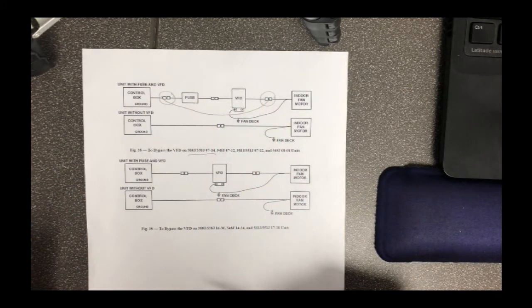Why? Because those fuses are not large enough to handle the locked rotor amps of this motor starting without the drive on it. You're going to blow those fuses, and they're not cheap fuses. So if you have the inline fuses, bypass those as well. Then get the new drive, plug the new drive in, and reprogram the drive.